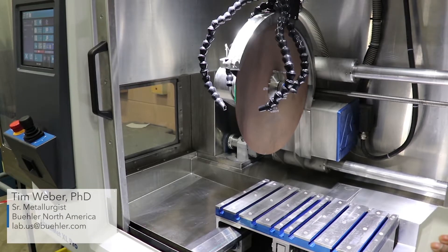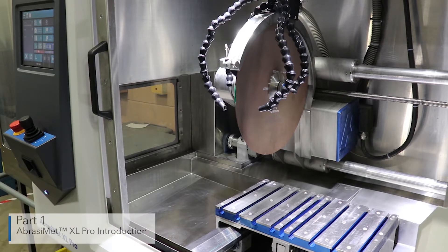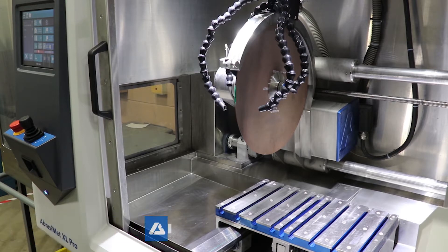Today we're going to talk about the Buehler AbrasiMet XL Pro heavy-duty abrasive cutter. This is a large abrasive cutter designed for high-volume applications. A few of the design features to talk about here: a 13 horsepower motor, blade sizes ranging from 14 to 18 inch size, and a very easy-to-use interface for control of the machine.